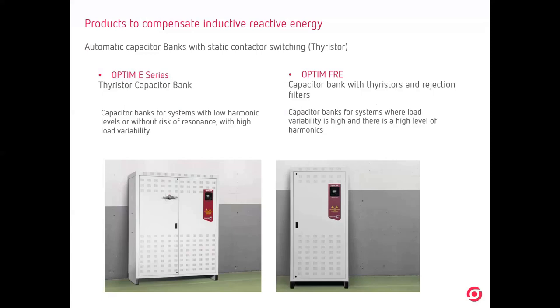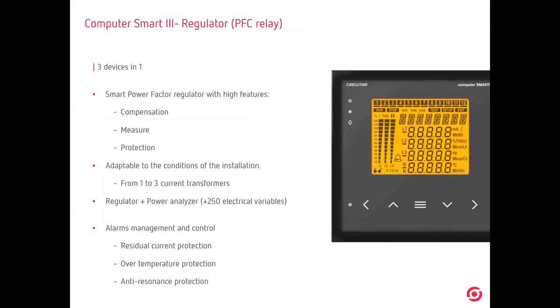So the best decision, if you don't have information about the installation where you're going to offer a capacitor bank, because you have received some measurements and you don't know the type of loads inside the installation in the industry, is always go to thyristors, to static switching, okay? With or without filters, it will depend on the presence of harmonics inside the installations. And also take care about the brain. The brain of the capacitor bank is the regulator. We have Computer Smart 3, the power factor relay regulator.